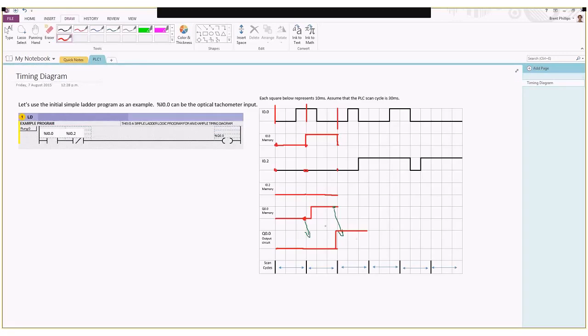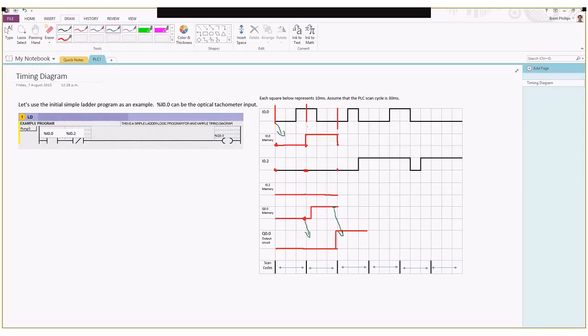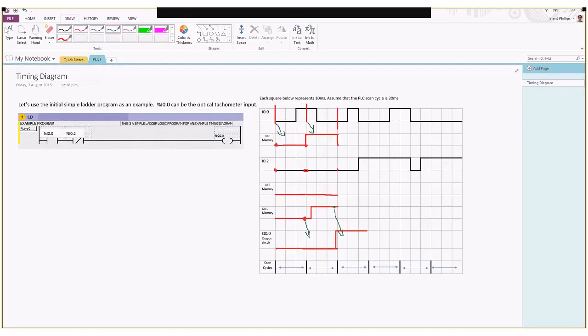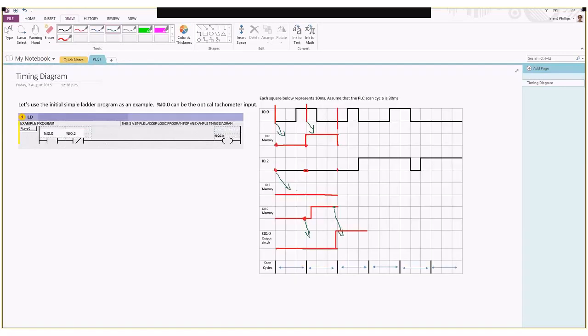You can see there's always these delay effects where the value of our input gets held in memory. We have this delay where whatever this value of the input is, that value gets stored in the memory of the PLC, and it's a combination of these memory values that actually gets used for solving the logic.